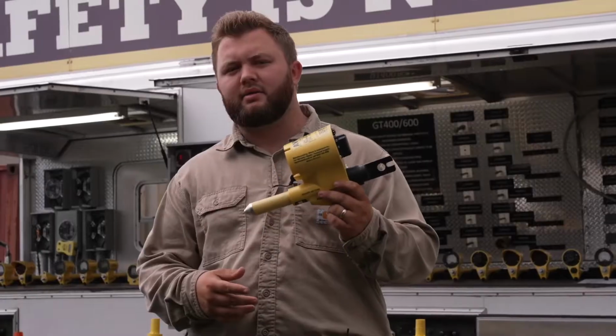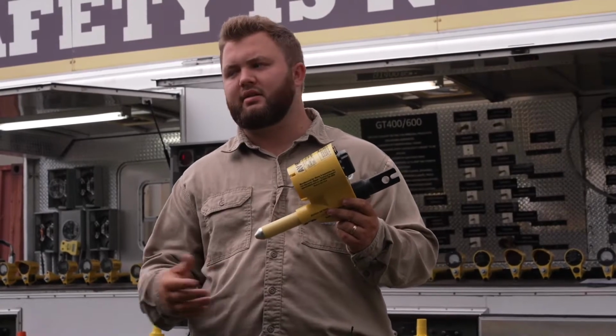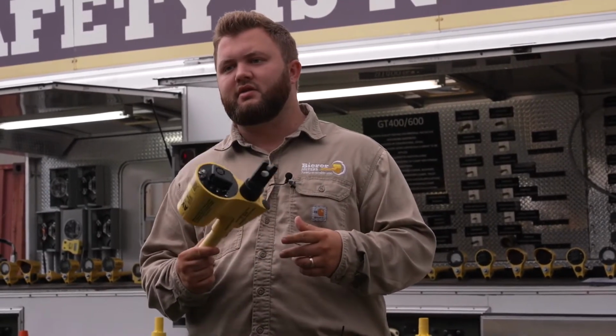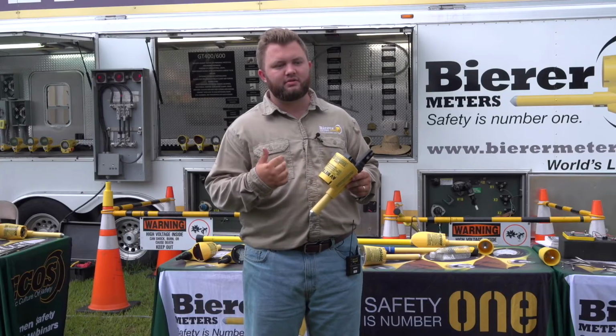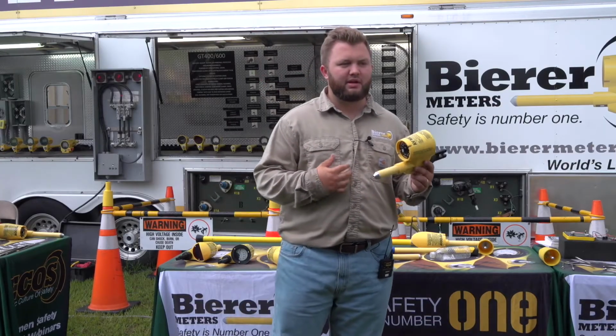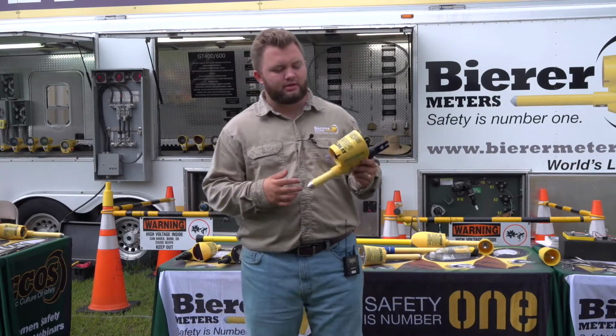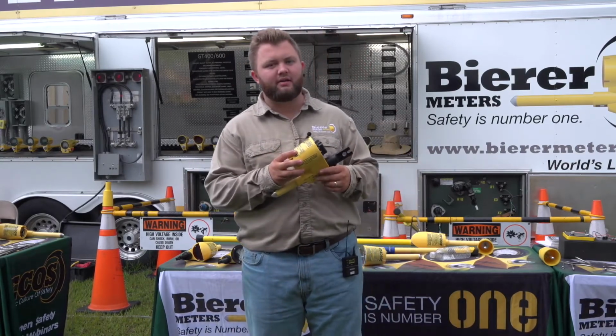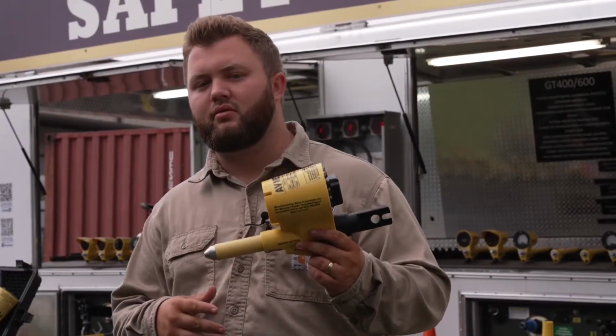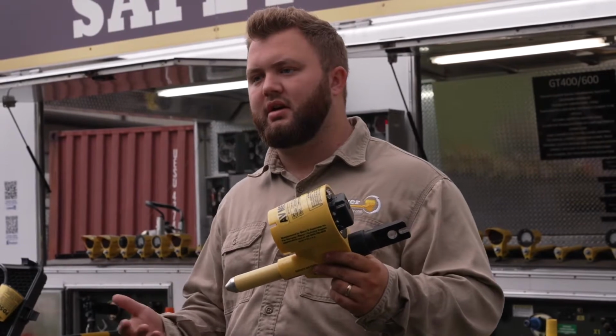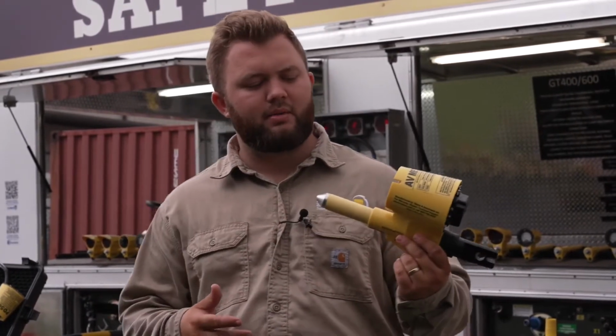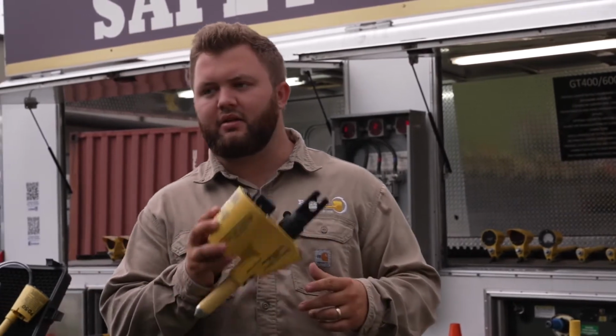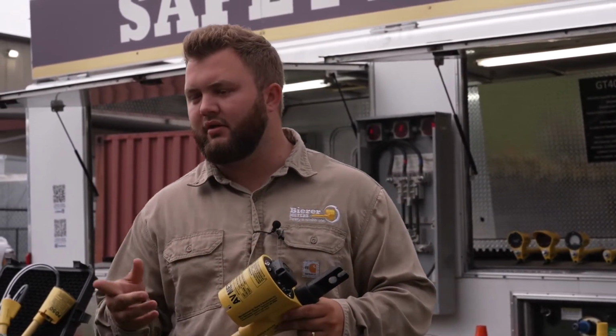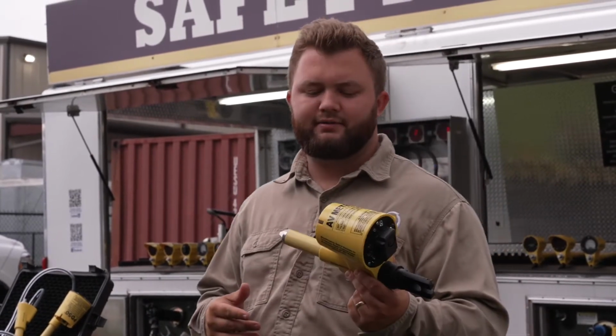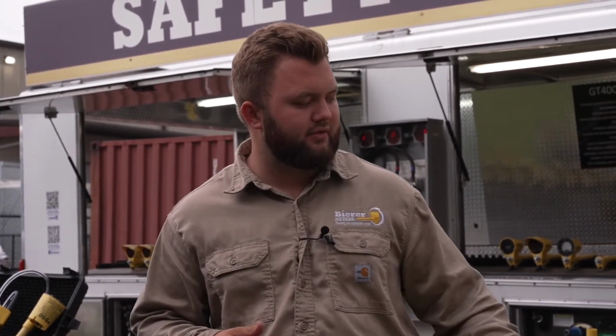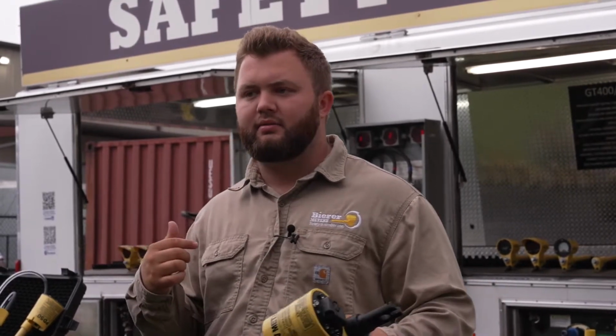But we hear a lot about folks getting these tools and telling their guys, hey, perform a battery test. If the tool checks out on a battery test, it's good to go, it's good to use. As the manufacturer, we know that's not entirely true. When you perform a battery test, you're just checking the battery, and maybe about 90% of the tool with our device, less with other users, could be more. But with ours, again, you're not giving the tool a true tool test, and we'll go over in a bit how to perform a true tool test on a live known voltage source, whether it's a tester or an energized conductor.